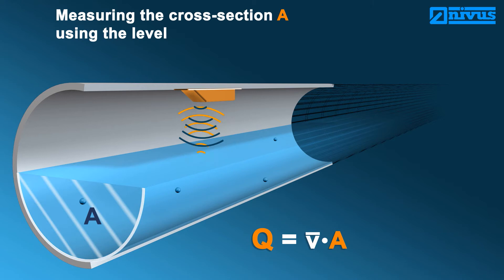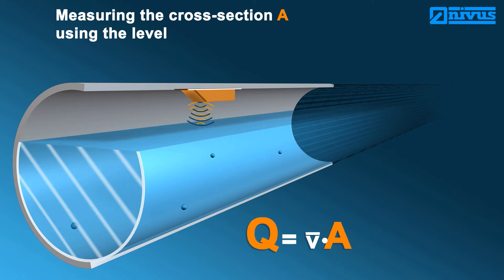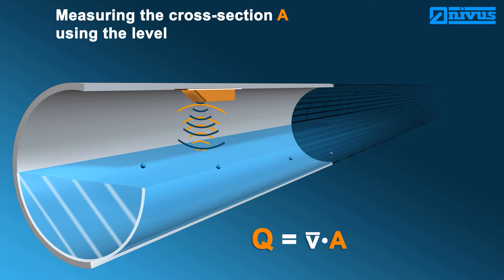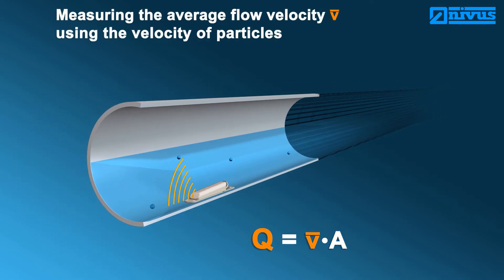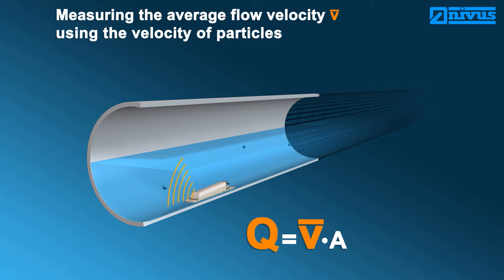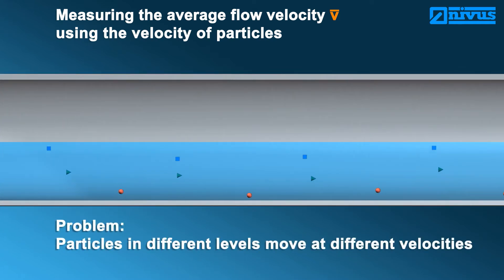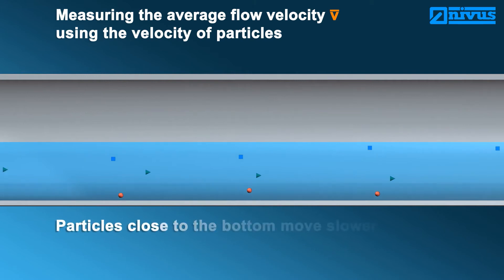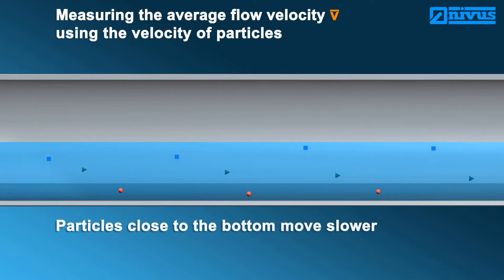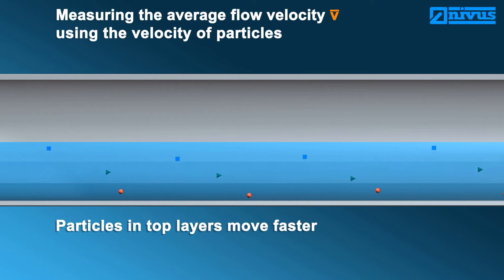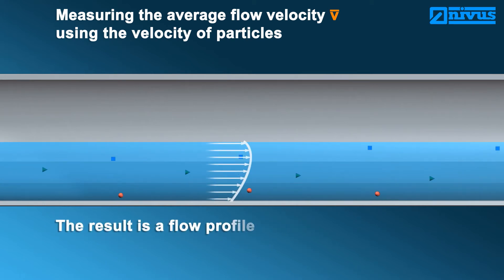The flow velocity is detected by measuring the particle velocity. Most media, particularly wastewater, contain dirt particles or gas bubbles moving with the same velocity as the medium. The velocity of the particles is measured using ultrasound. As soon as the velocity changes, the flow normally changes as well. The main difficulty while detecting the average flow velocity is that there are varying velocities prevailing at varying levels. The medium and hence the particles normally flow slower at low levels than at higher levels. From this, a so-called flow profile can be obtained.